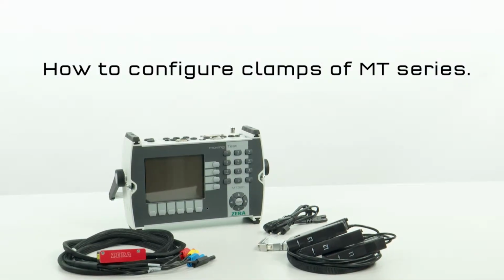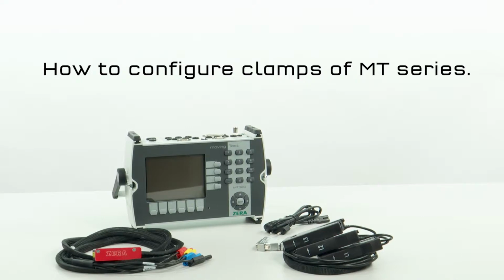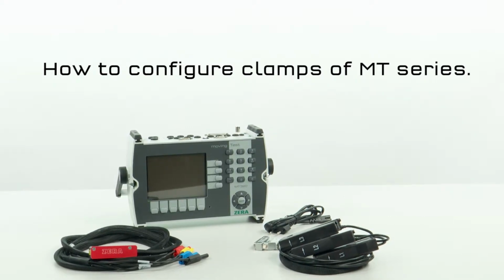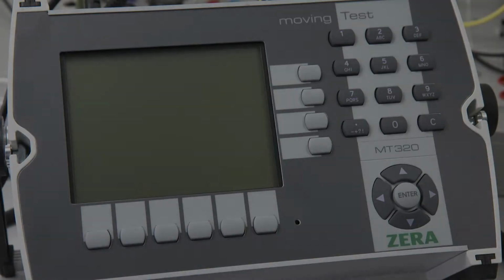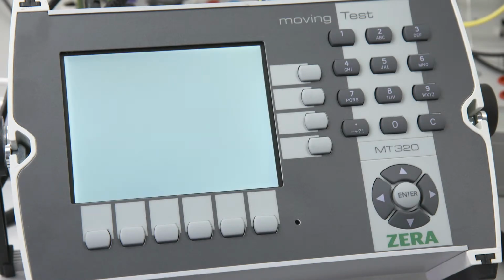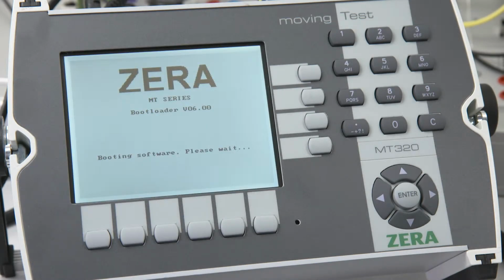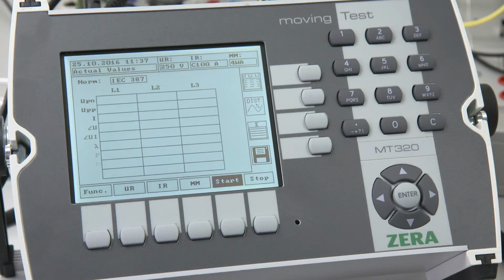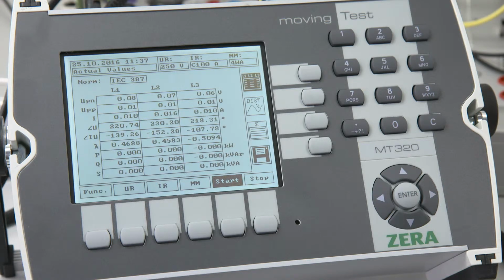This tutorial explains how to configure the clamps of the MT series correctly. After switching on and finishing the boot sequence, the device is set to the highest voltage and current range by default. The measuring mode is set to 4-wire active.